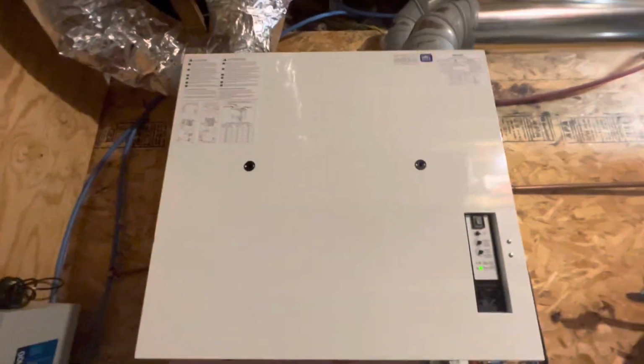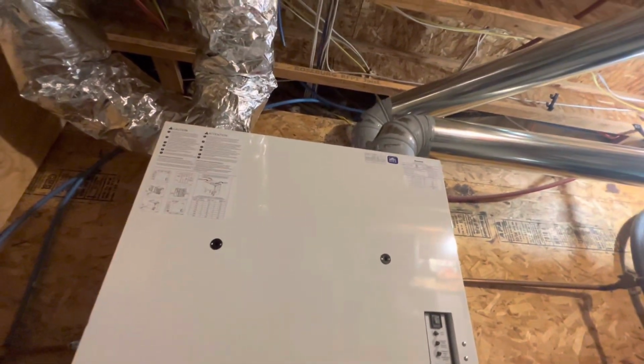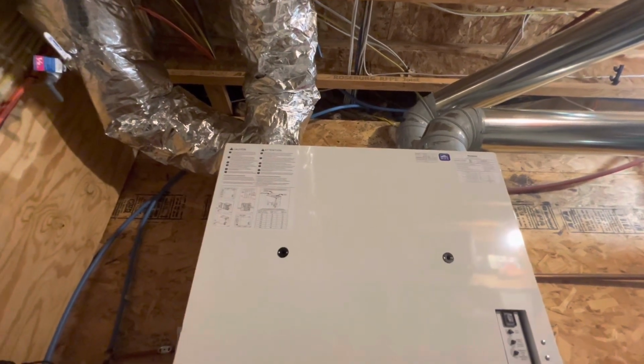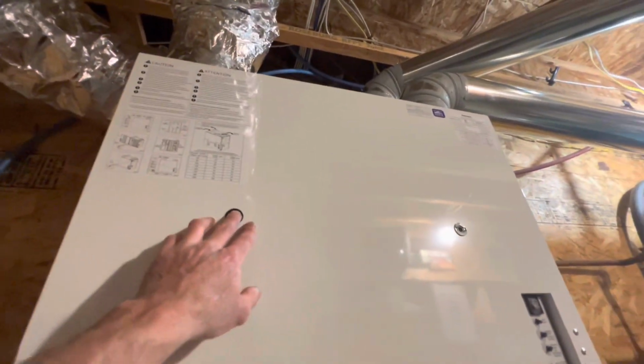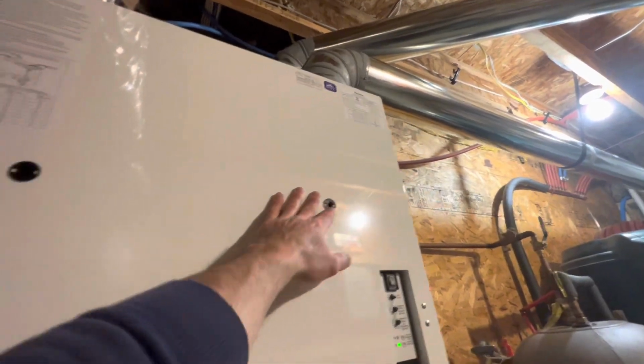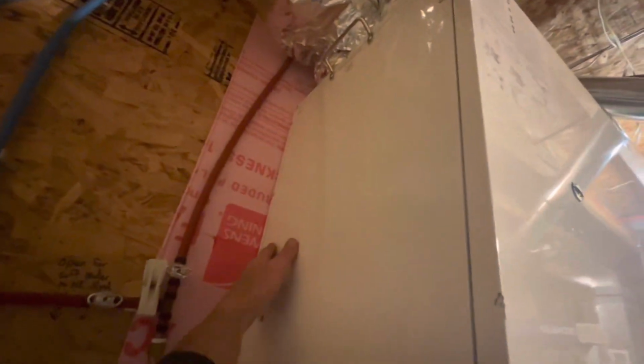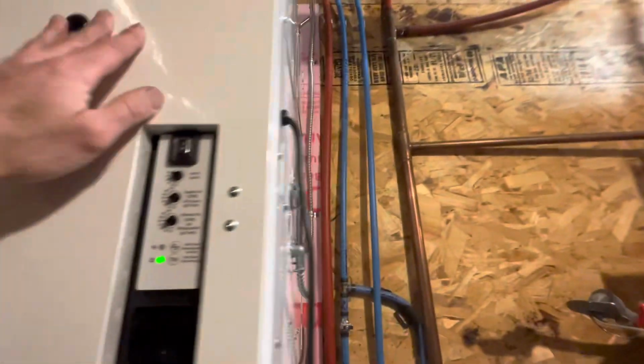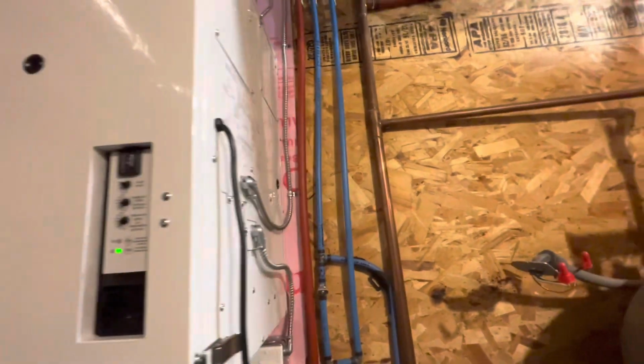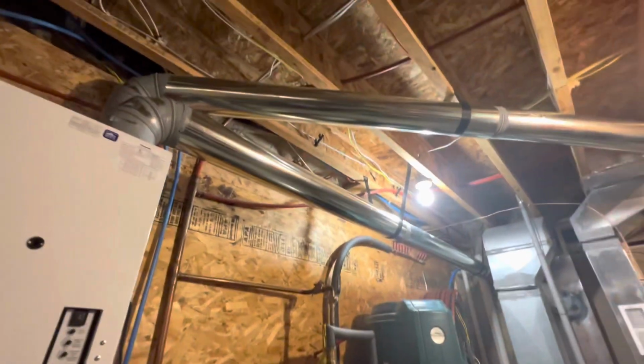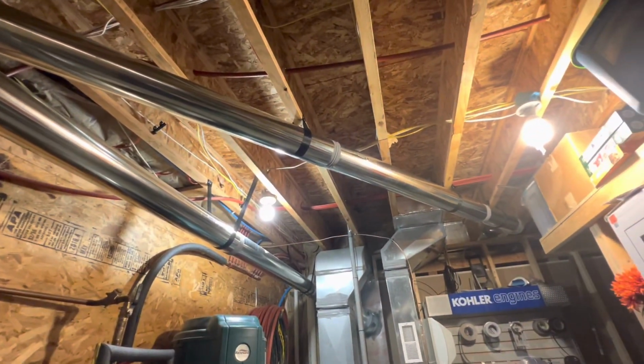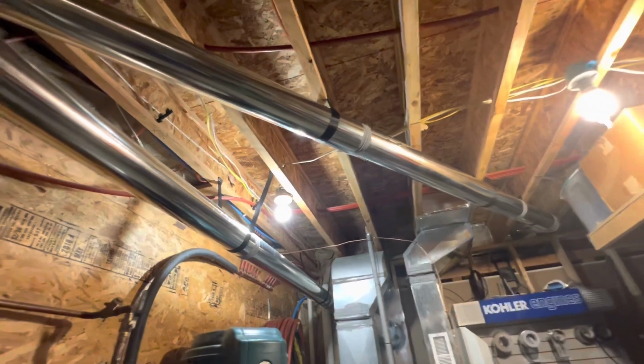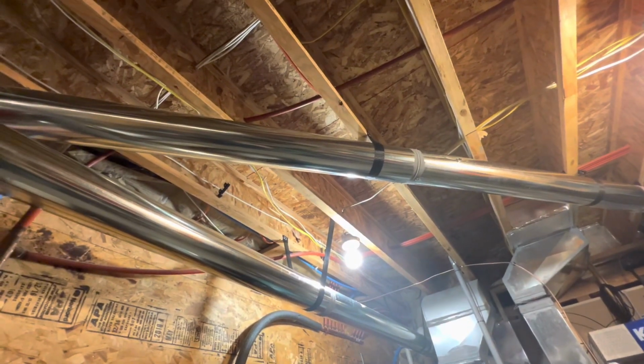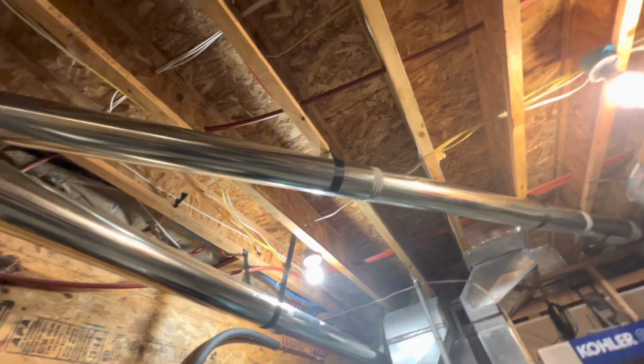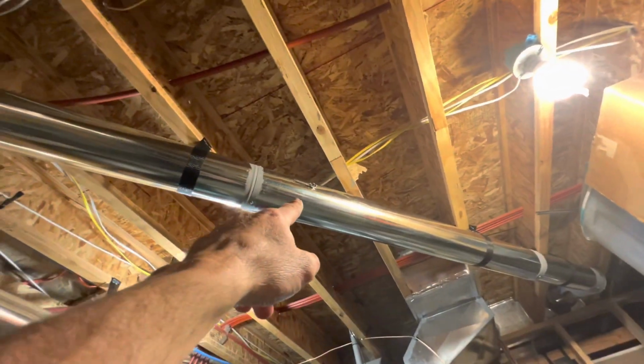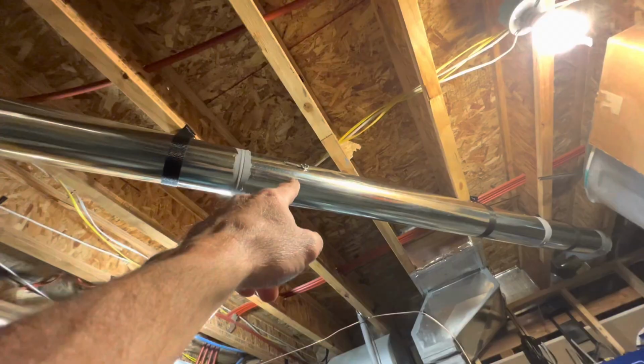So one thing I haven't done yet is calibrate the ductwork pressures. That's what these ports are for. There's essentially one in all 4 of the chambers: 1, 2, 3, 4. So the way I installed my unit, I really only have one damper that I would need to adjust to get the pressures to where they need to be. That would be on this ductwork line here. You can see that damper there.